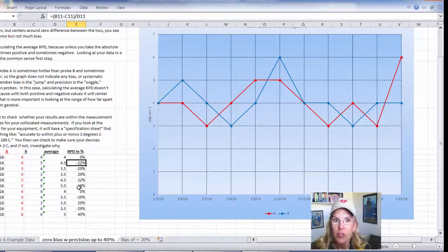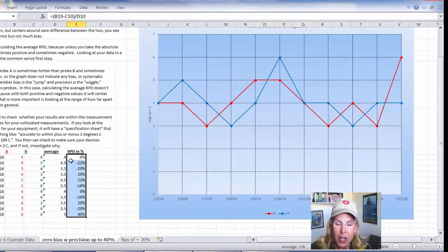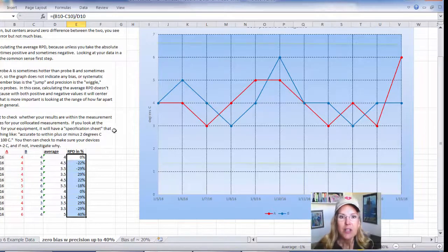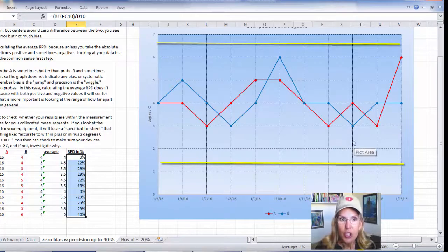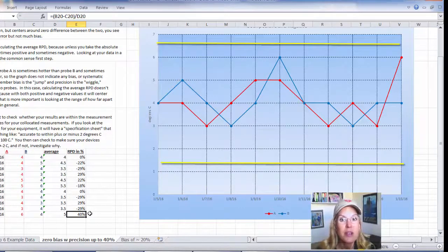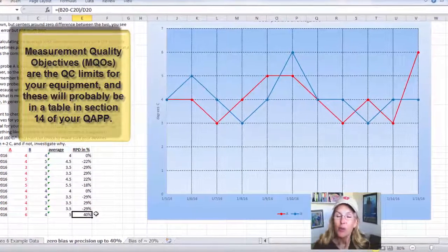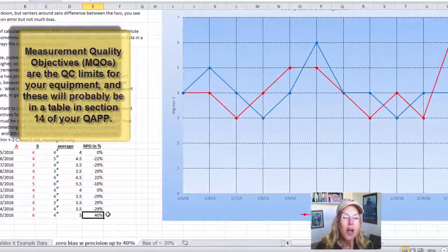One of the things you need to do in your QC checks is make sure your results are less than a particular limit. Sometimes that limit might be two degrees — an absolute number of degrees that your two temperature probes can differ by — and sometimes that's a value in percent. In general, what you look for is having your QC results meet a certain standard for how well your devices need to perform. You would plot a control chart like this to make sure your relative percent difference is less than a certain percentage, and you could easily scan down to see when it exceeds that amount. This will be written up in your QAPP, probably in section 14, in a table called Measurement Quality Objectives.